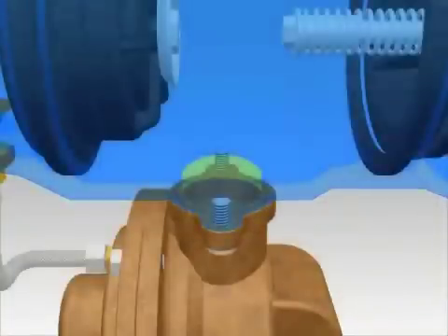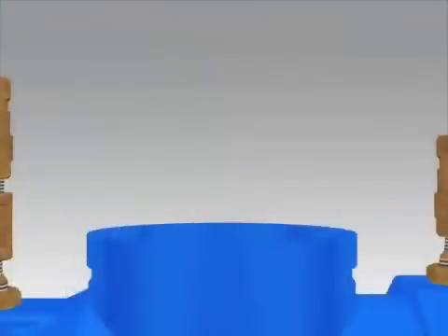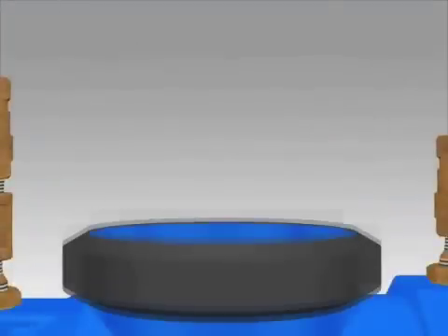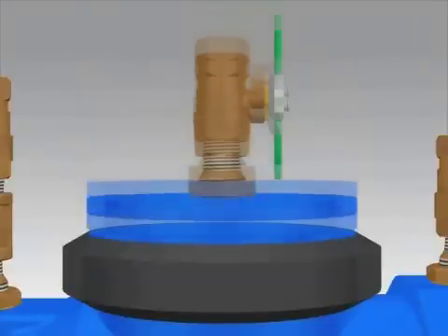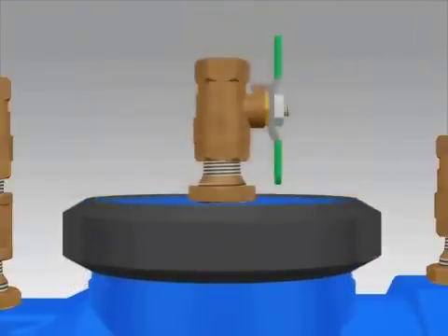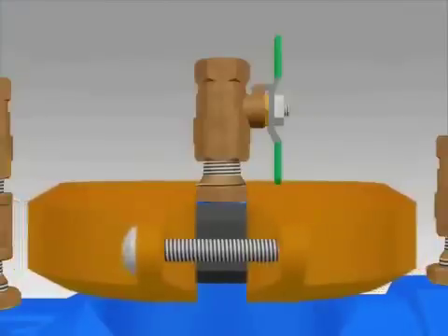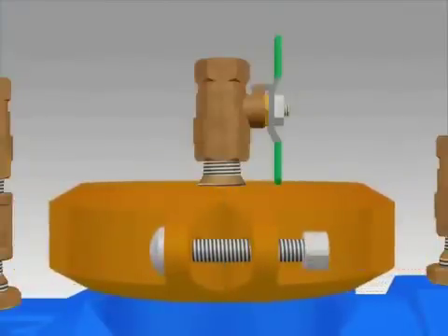Remove the rag in the body opening. Place the groove coupling gasket over the valve opening. Lubricate the outside of the gasket. Replace cover and reassemble groove coupling. Make sure coupling is seated properly and the ends of the coupling halves touch.